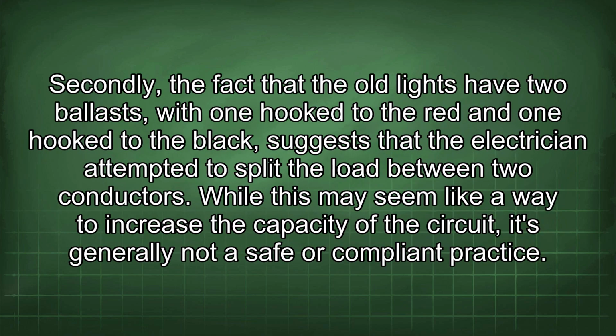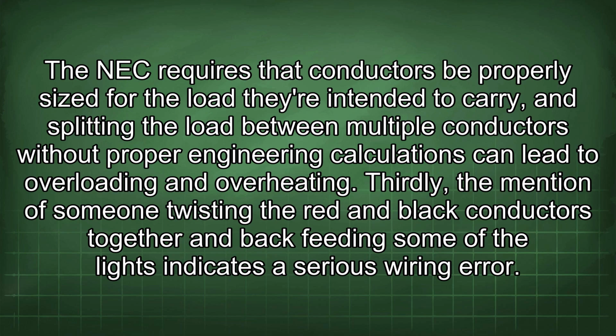Secondly, the fact that the old lights have two ballasts, with one hooked to the red and one hooked to the black, suggests that the electrician attempted to split the load between two conductors. While this may seem like a way to increase the capacity of the circuit, it's generally not a safe or compliant practice. The NEC requires that conductors be properly sized for the load they are intended to carry, and splitting the load between multiple conductors without proper engineering calculations can lead to overloading and overheating.